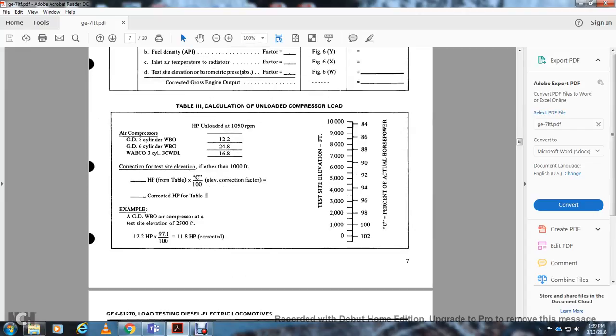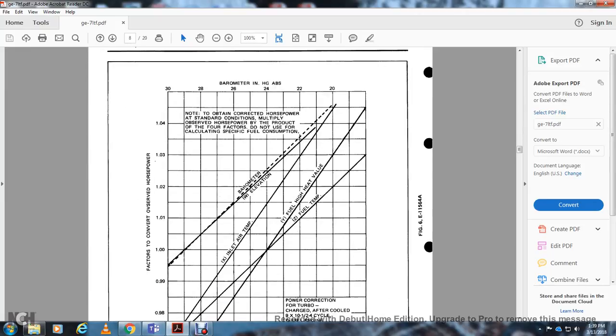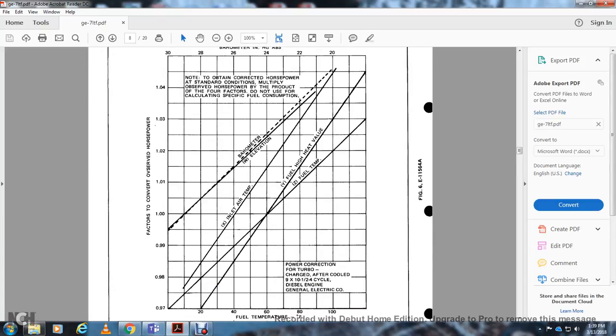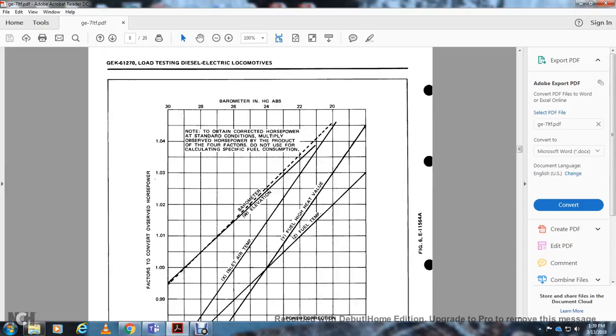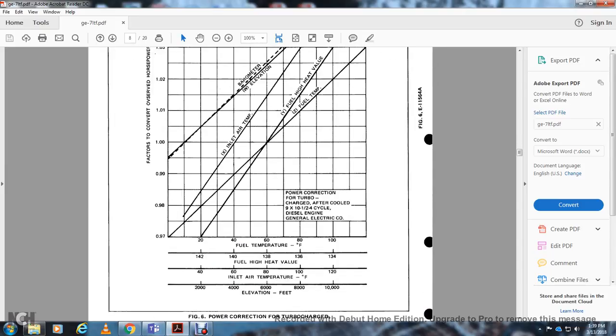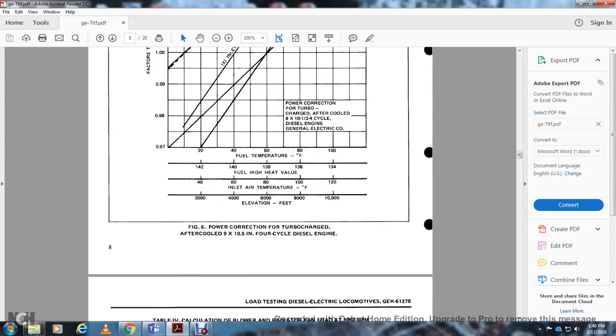Alright, we're looking at the scale on the right. You have the calculation unloaded compressor load, the test site elevation feet, percent of the actual horsepower. Then you have your barometric reading, which is bottom line W, inlet temperature, X line, fuel heat line Y, Z fuel temperature line. Factors to convert the observed horsepower, in increments of a half a point on the horsepower observed curve. You have your fuel temperature, your heat value, inlet air temperature, and elevation feet. This is your correction for your turbocharger.